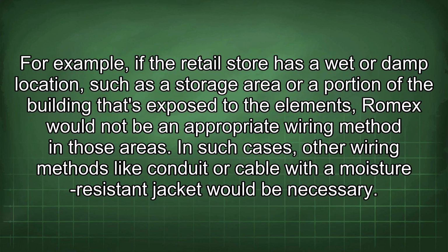For example, if the retail store has a wet or damp location, such as a storage area or a portion of the building that's exposed to the elements, Romex would not be an appropriate wiring method in those areas. In such cases, other wiring methods like conduit or cable with a moisture-resistant jacket would be necessary.